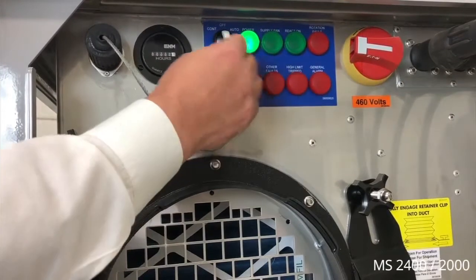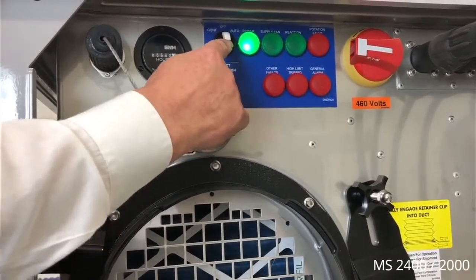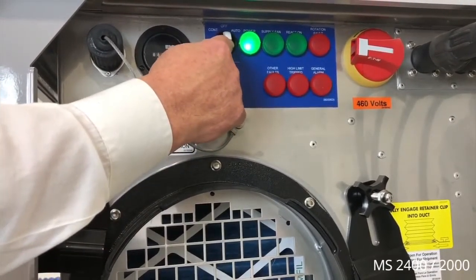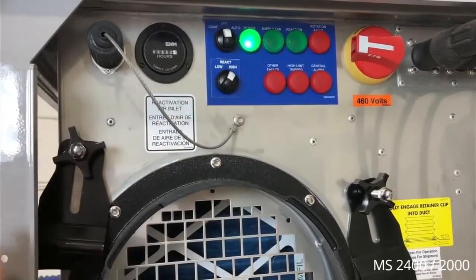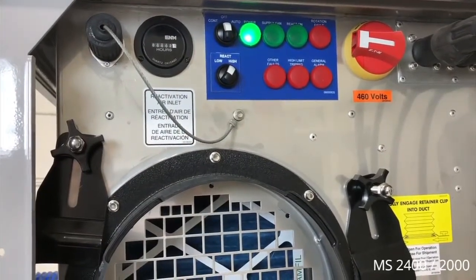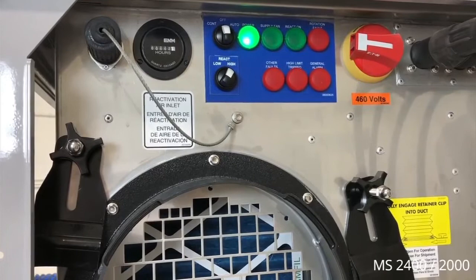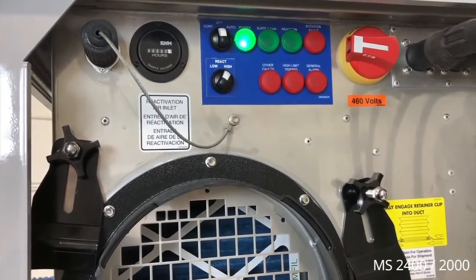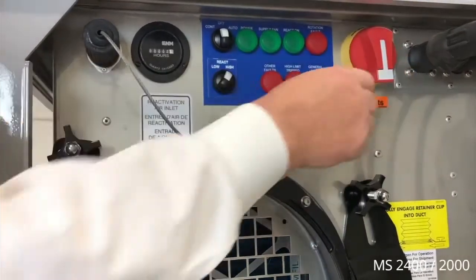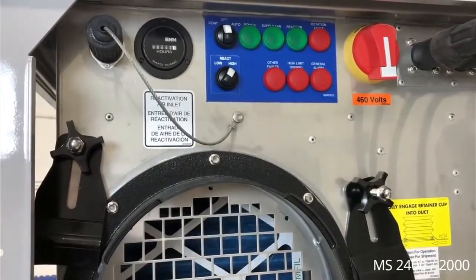The proper way to turn the unit off is to turn the operational switch to the off position. This will allow the reactivation fan to spool down for 2 minutes and cool the electric heaters before the unit actually shuts down. Then it's safe to throw the main power disconnect and disconnect the power from the dehumidifier.